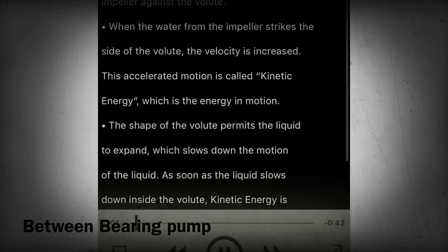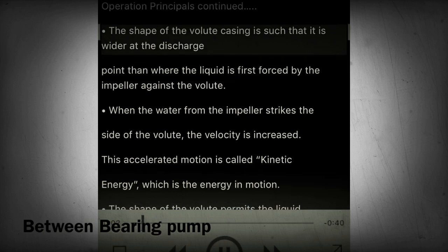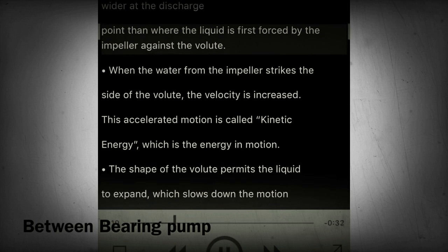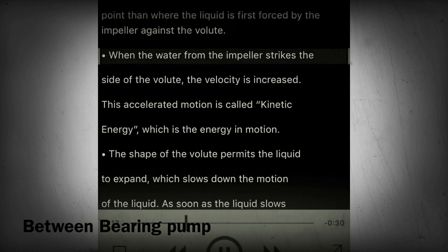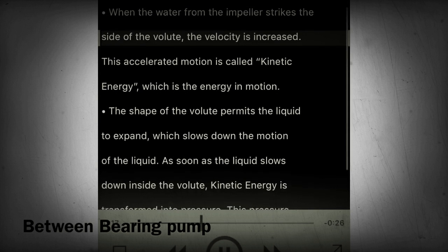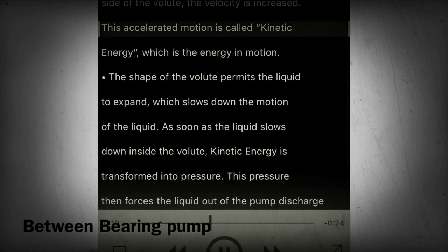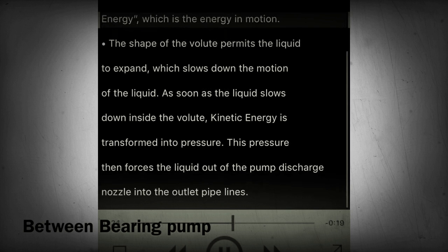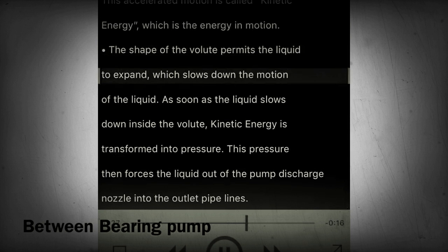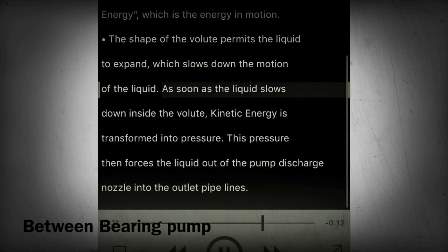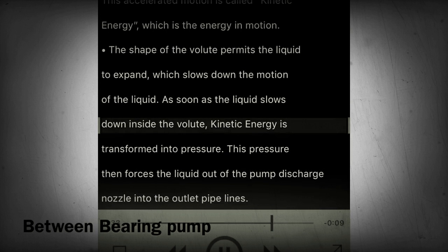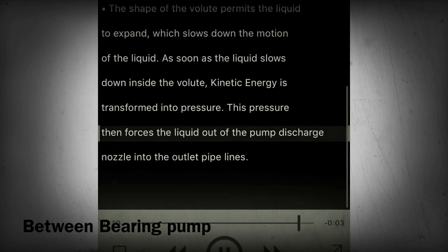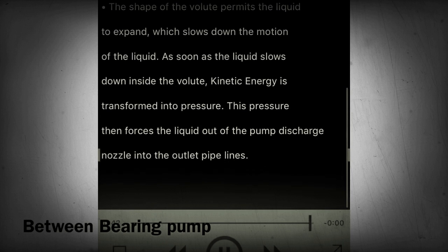Section 17 - Operating principles continued. The shape of the volute casing is wider at the discharge point than where the liquid is first forced by the impeller against the volute. When the water from the impeller strikes the side of the volute, the velocity is increased. This accelerated motion is called kinetic energy, which is the energy in motion. The shape of the volute permits the liquid to expand, which slows down the motion of the liquid. As soon as the liquid slows down inside the volute, kinetic energy is transformed into pressure, which then forces the liquid out of the pump discharge nozzle into the outlet pipelines.